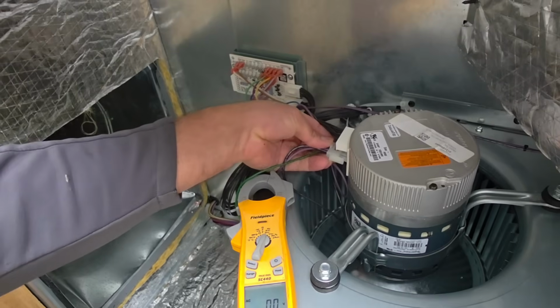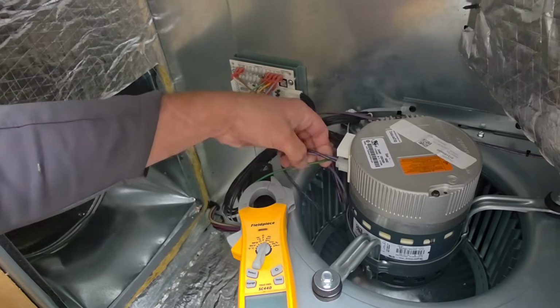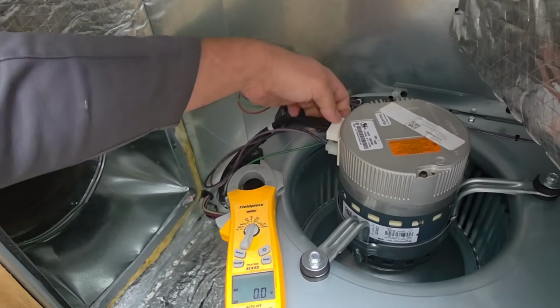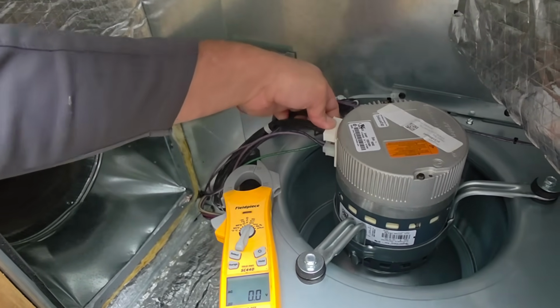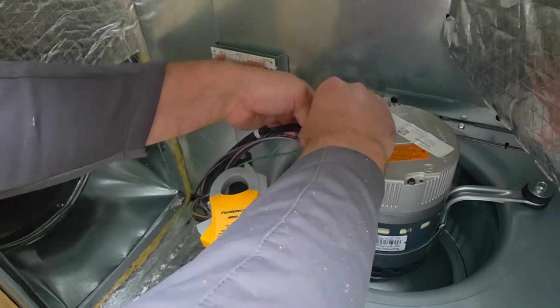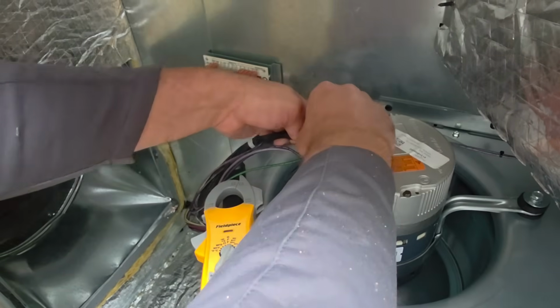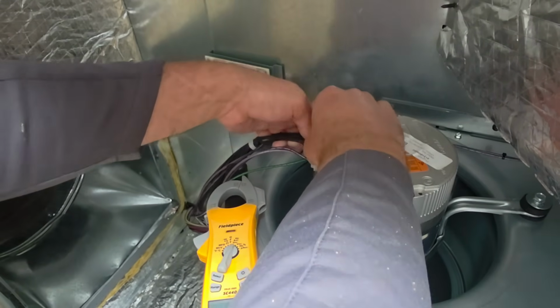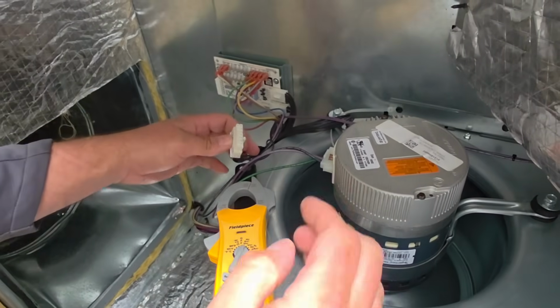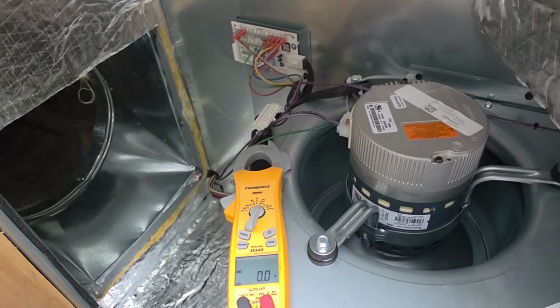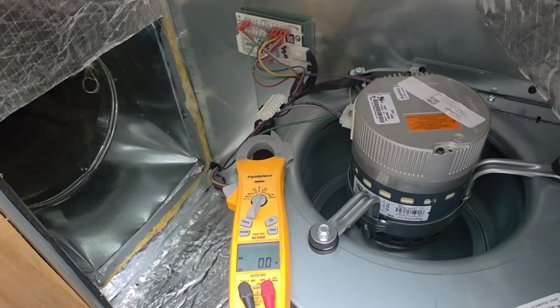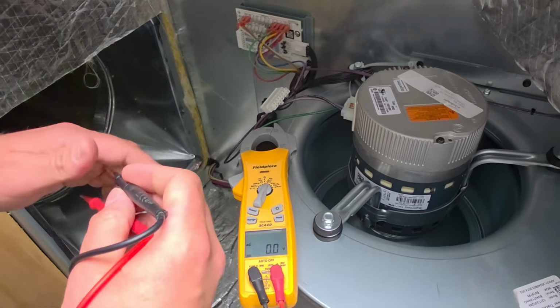Be careful when you are messing with the blower with power on. Now we're going to disconnect the 16 pin. This is our call to this motor, right? You got to have power, you got to have 240, and you got to have a call for it to run. If we disconnect this, it's not going to run, the power or the call.